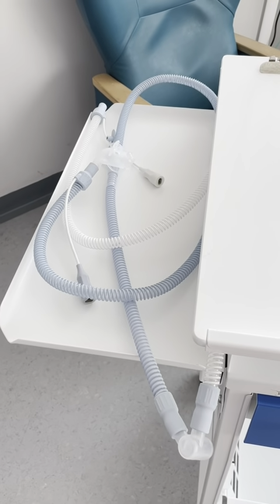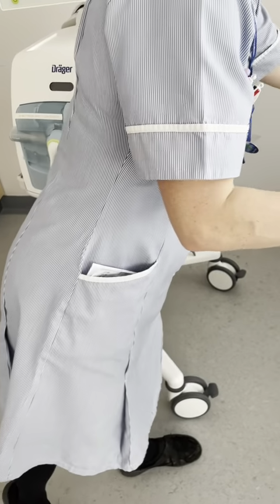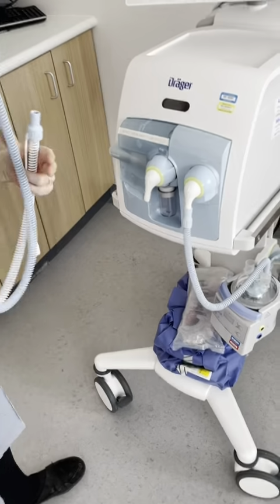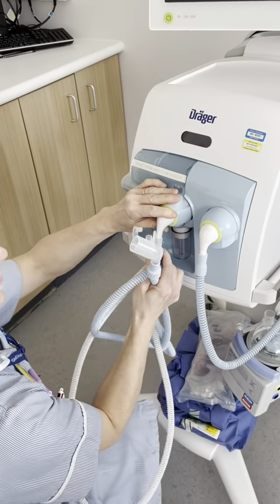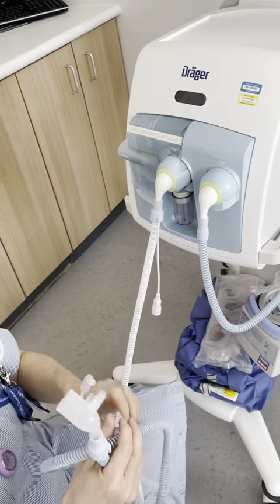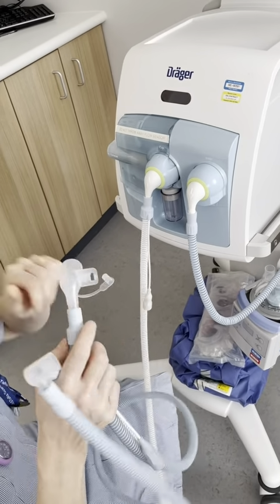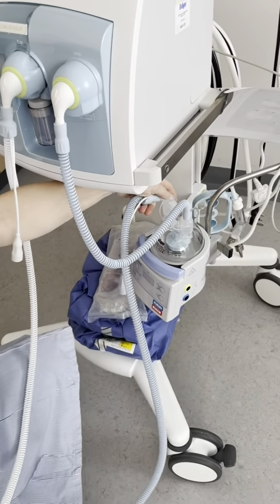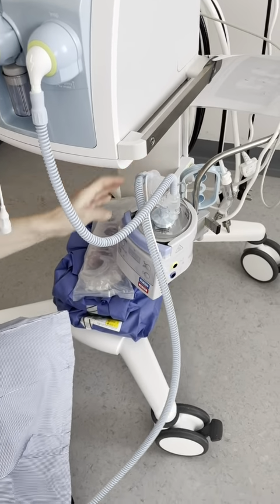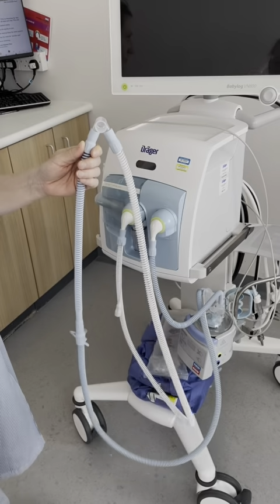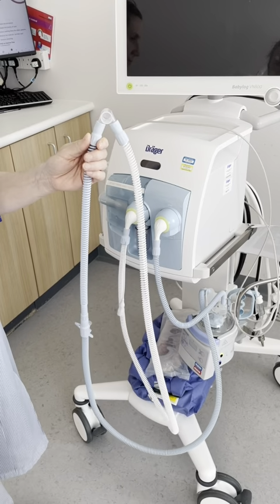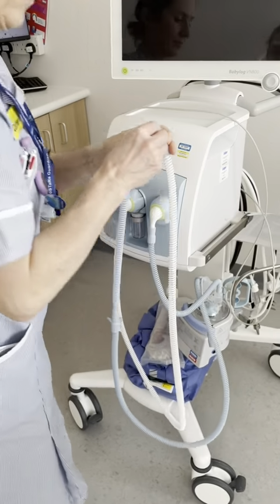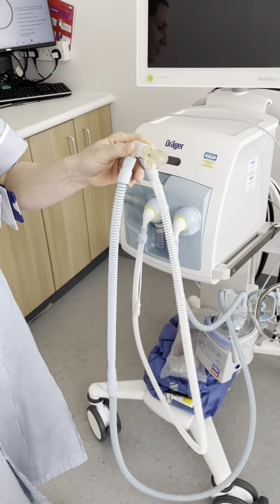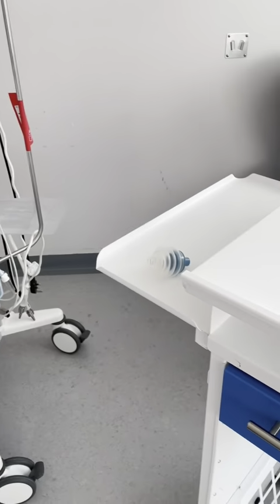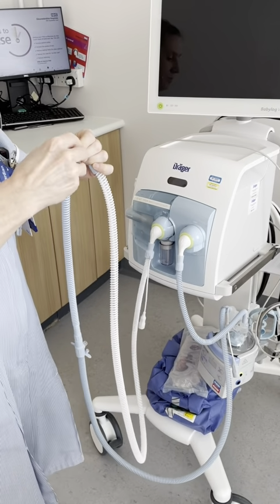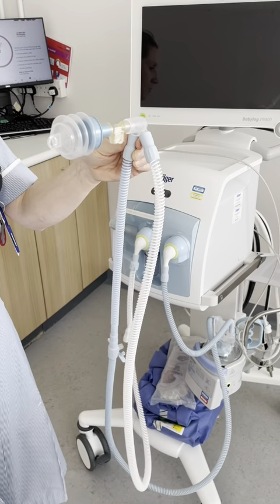The rest of the circuit tubing can now be attached. Add one end to the expiratory port and the other end to the humidification chamber. The sensor housing, which comes from CSSD, is now ready to be attached. It will only attach one way. Attach the test lung, which will enable us to test the ventilator and will also keep the circuit closed.